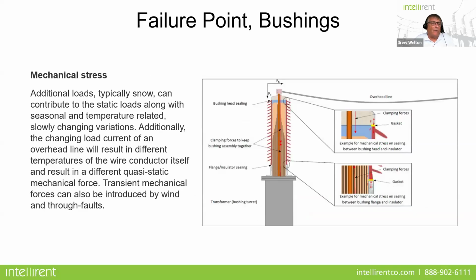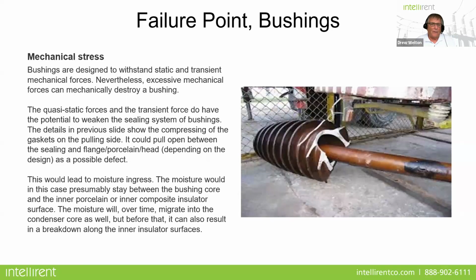So, mechanical stress. Additional loads, typically snow and ice, can contribute to the static loads along with seasonal and temperature related variations. The changing load current of an overhead line will result in different temperatures of the wire conductor itself and result in different quasi-static mechanical force. Transient mechanical forces can also be introduced by wind and, once again, through faults. In terms of mechanical stress, the bushings are designed to withstand static and transient mechanical forces, but nonetheless, excessive mechanical forces can mechanically destroy a bushing.